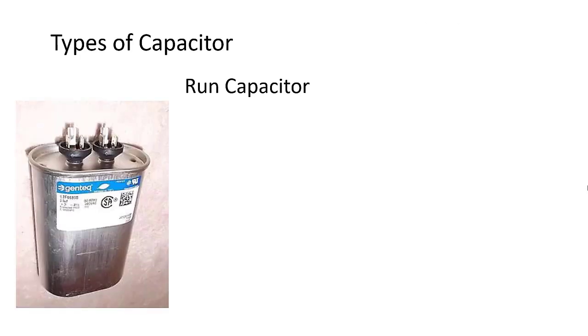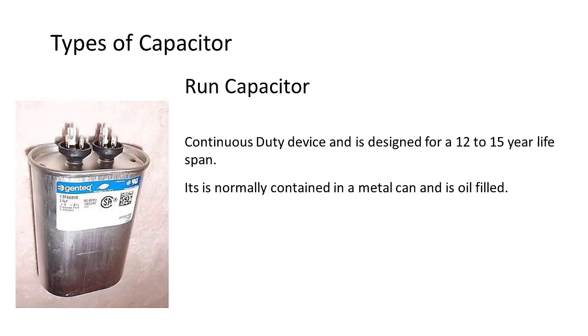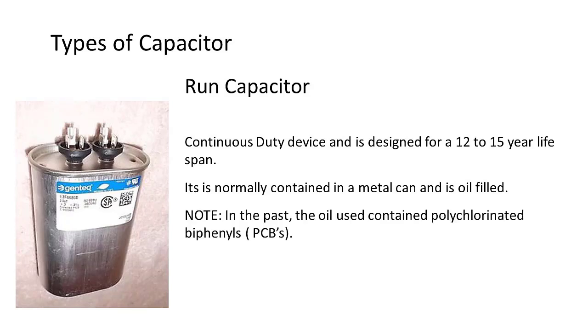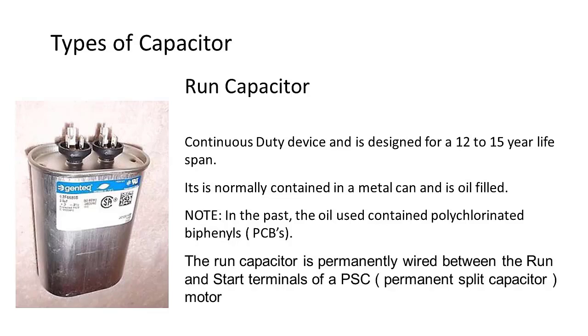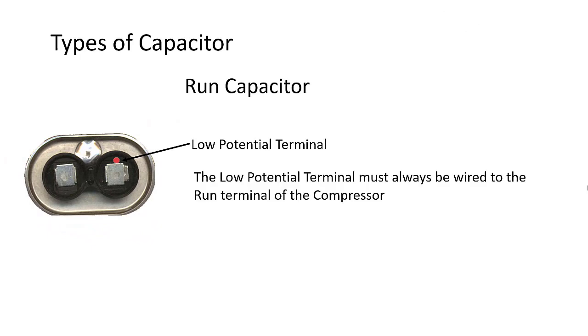Run capacitors are continuous duty and are designed for a 12 to 15 year lifespan. They are normally a metal can filled with oil. It should be noted that in the past the oil would contain PCBs, which can cause cancer. It would be rare to come across one today, but you should be aware of this. The run capacitor is permanently wired between the run and start terminals of a permanent split capacitor motor. Run capacitors have a low potential terminal, and it should always be wired so it connects to the run winding and not the start winding.